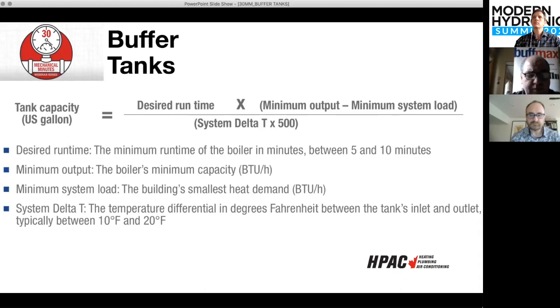So it's done by aquastats. You can turn pumps on, and as Steve said, you can do multiple demands off the tank. So it's not just a tank. There is purpose to it other than being a buffer. It helps the whole system run a lot more efficiently if it's done and controlled properly.